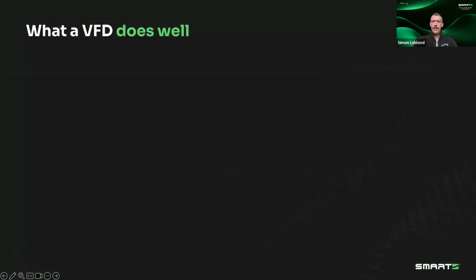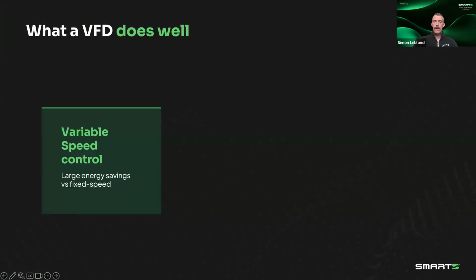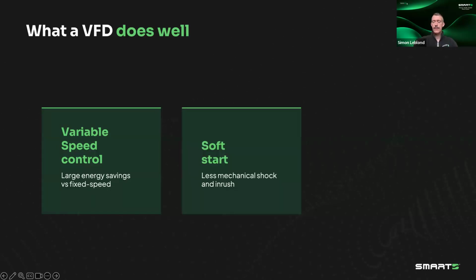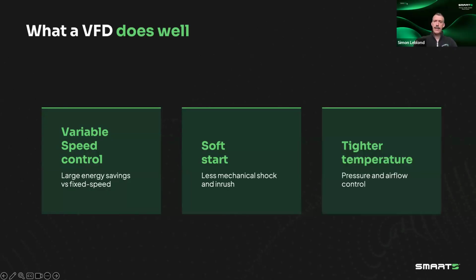First, let's all recognize that VFDs have been growing and are performing superbly well because they really offer large energy savings for all of these variable speed loads. So that's right for them to put in. They also offer a soft start, so you've got no electrical shock to your motor. You extend their life, and you also have much better airflow control. So all of these reasons make VFDs the right choice, and you're right to put them in the cooling plant.